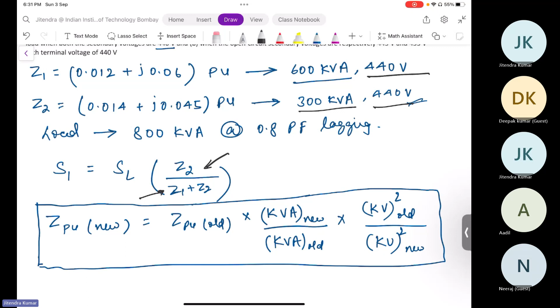Now I would like to compute Z2 per unit new. Its old value is 0.014 plus j0.045. kVA new is 600, and kVA old was 300, and kV old and kV new are both the same, so we don't have to worry about that.